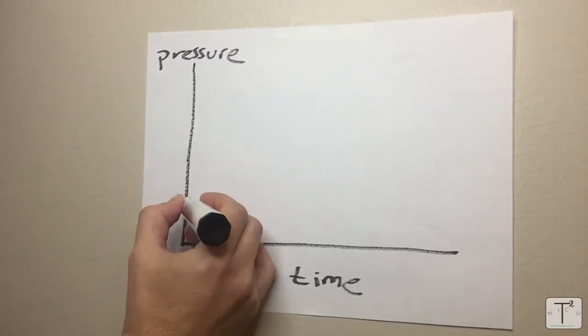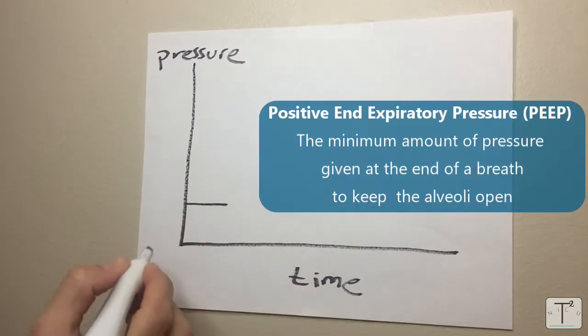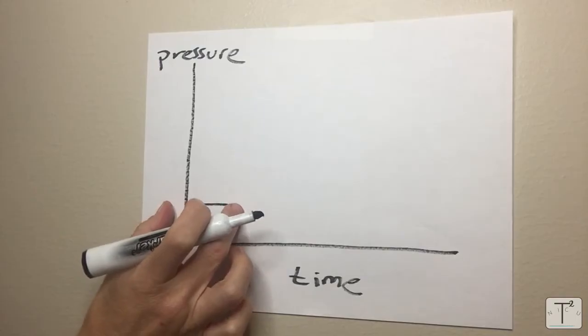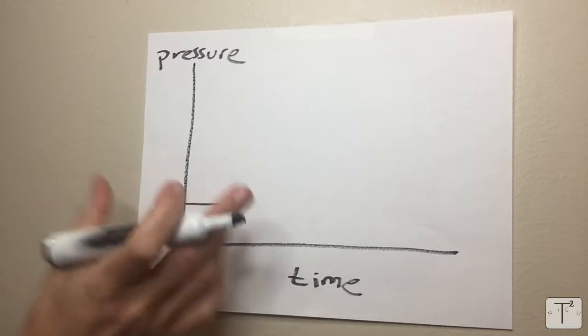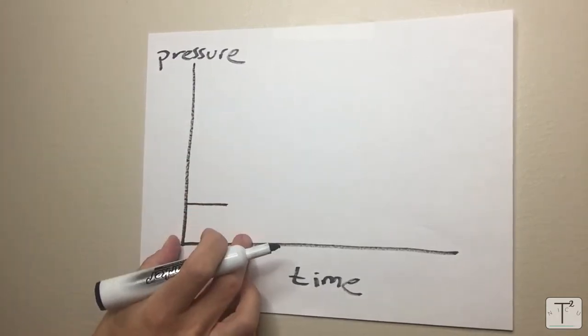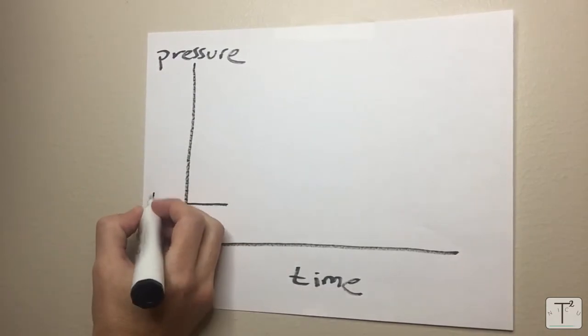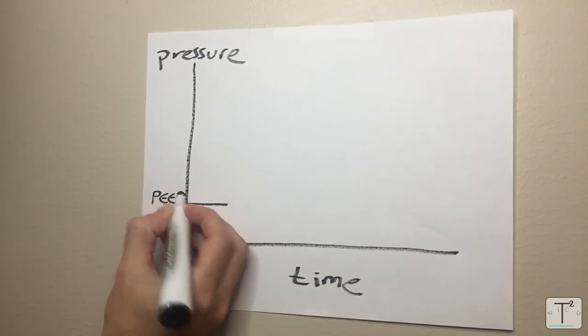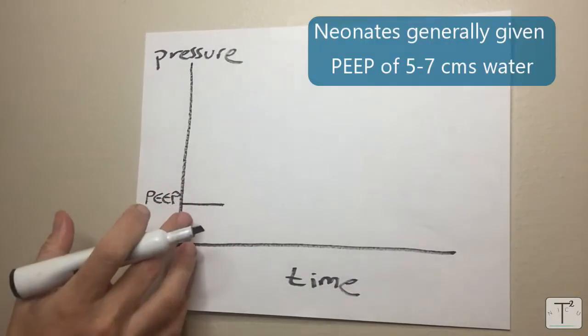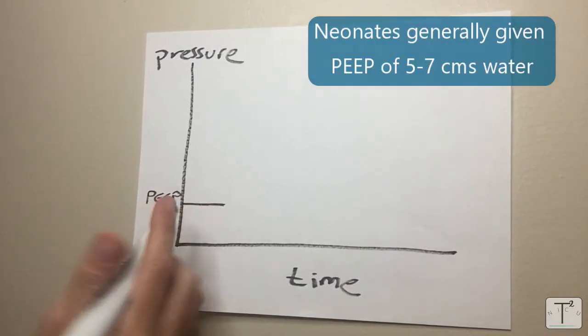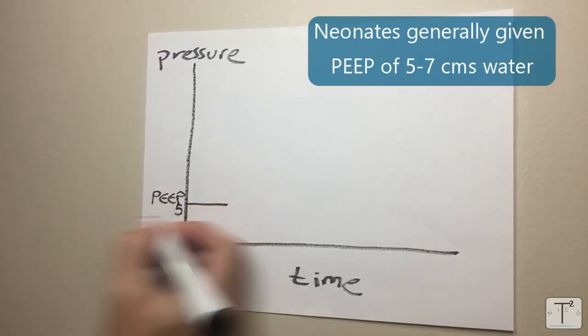As time moves forward the machine is going to give different amounts of pressure to the baby. The first thing that we have to determine is what we want our positive end expiratory pressure to be. That is the pressure that the machine gives at the end of the breath, the minimum pressure to try to make sure that the alveoli stay open. It's kind of like the functional residual capacity in a normal lung. Here let's call that the PEEP. In neonates normally we use a PEEP somewhere between five and seven centimeters of water. In this case let's assume that our PEEP is five.